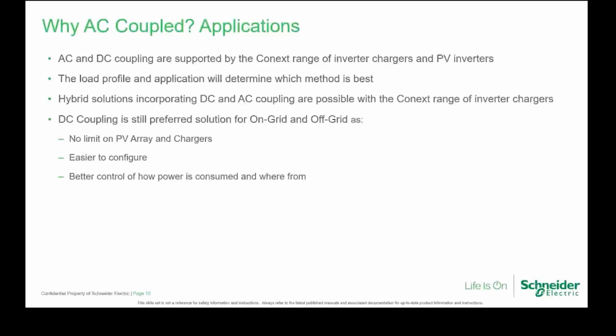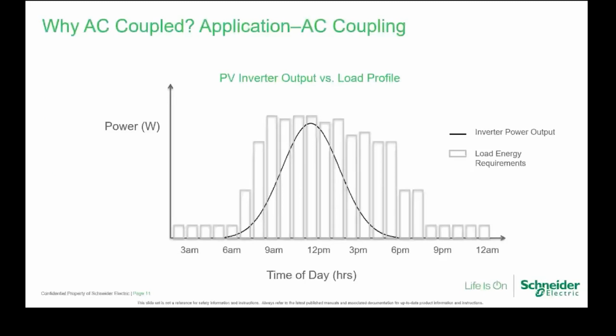That's the thing you need to do before you look at which specs you're going to use. You're going to work out what your load profile is, how you, the end user, are using energy during the day and during the night time. We can see over here where we have the energy being used, the load energy requirements match up with the inverter power output. That would be more suitable for an AC coupling solution because you're using the energy directly from the PV array and you're not actually charging and discharging the battery, which means you become more efficient.